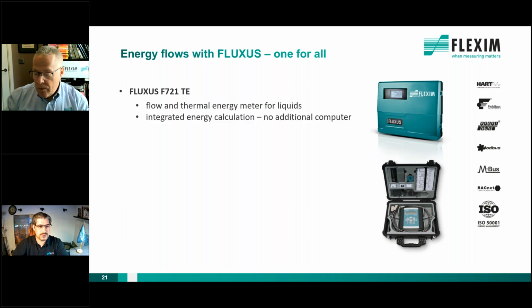And I'm going to show you some products here. We already learned about the gas flow measurement for oxygen or for nitrogen, for example, but we have different configurations. For example, the Fluxus F721TE. TE stands for thermal energy, which is a fully integrated flow and energy meter. So you have an internal energy calculation. You can plug in two temperature probes, PT100 or PT1000. You can even plug in external 4 to 20 milliamp signals, and then let the meter calculate your energy flows, even up to a 2-channel meter, so that you can handle 2 different measuring spots with 1 meter.